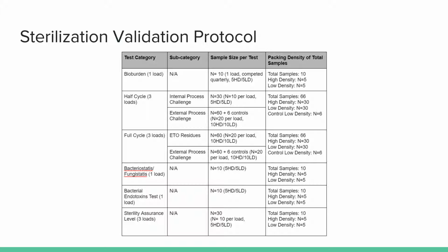Next, the team needed to verify the sterilization method was sufficient for the intended use. EO sterilization will be used because it is best suited for the materials in the device and the fact that the device is only cleared for a single use. A variety of tests will be conducted, some of which, like bioburden, will be conducted at regular intervals to ensure that the sterilization standards are continuously met.